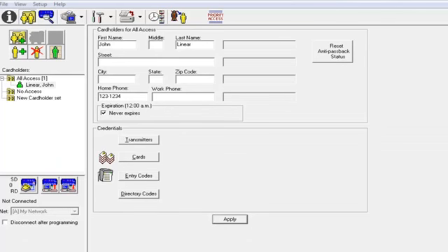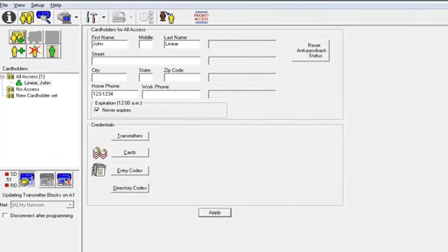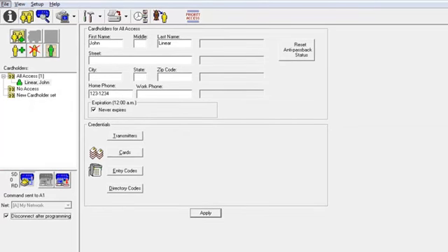After selecting this icon, we can see a number appear between SD and RD, representing the number of data packets the AccessBase 2000 software is sending to the panel. This number will start to decrease. Once it reaches 0, the startup process is complete.